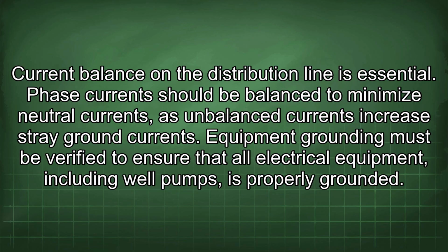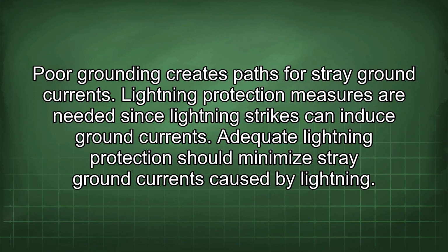Current balance on the distribution line is essential. Phase currents should be balanced to minimize neutral currents, as unbalanced currents increase stray ground currents. Equipment grounding must be verified to ensure that all electrical equipment, including well pumps, is properly grounded. Poor grounding creates paths for stray ground currents.